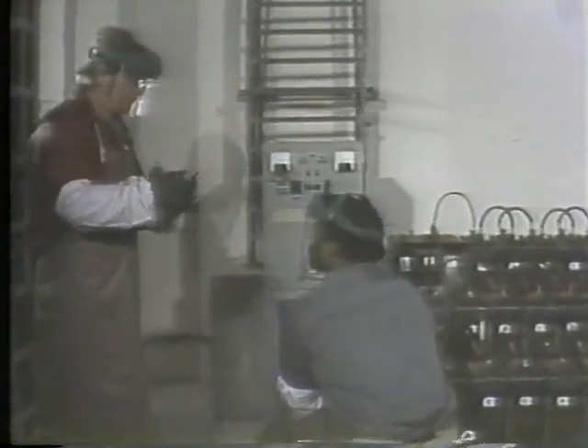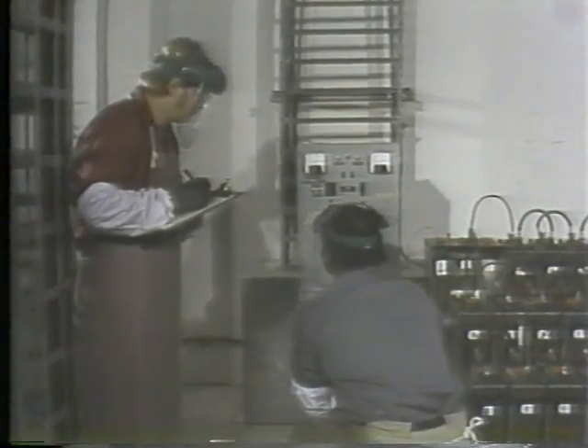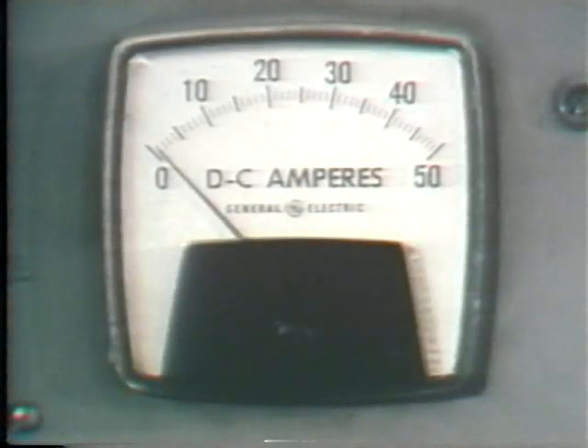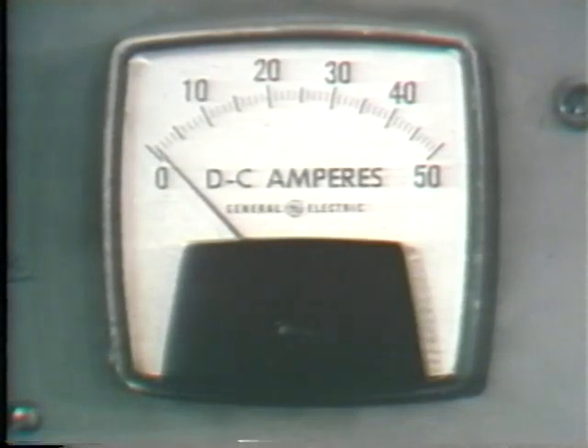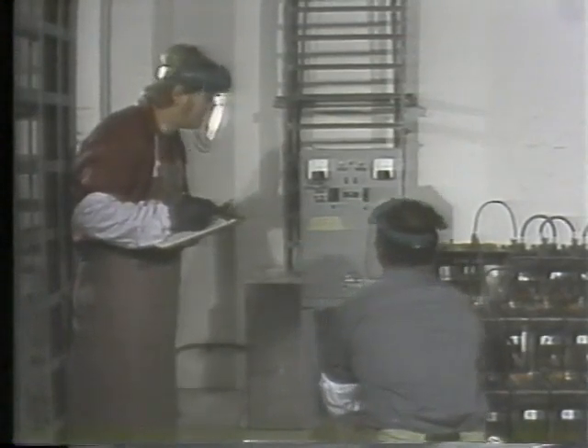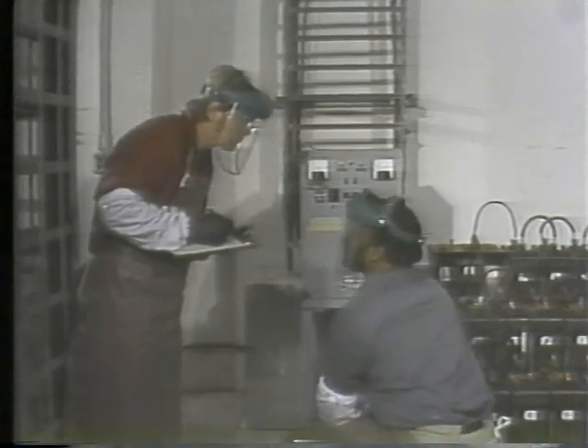For this initial inspection, one worker keeps the records while the other takes readings. The first thing they have to check is the float voltage — if it's set too low, the battery won't be getting a full charge; if it's set too high, the battery may be damaged by overcharging. The ammeter on the charger gives an indication of the battery's present condition. It should reflect the normal station load plus a small trickle current through the battery.